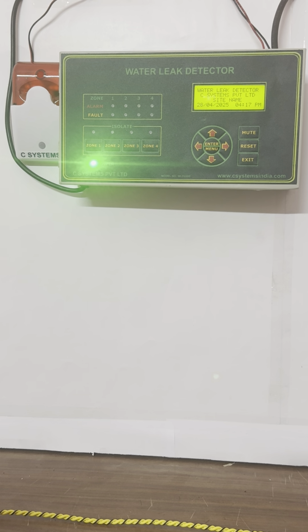I'll explain in detail the panel fascia features as well as the hardware input output features in the water leak detection system. The panel is equipped with a 4x20 LCD display and keypads with LED indication for each zone, alarm and fault condition. Apart from the alarm and fault indication, there is a provision for isolating each zone individually, which is provided in the zone 1 to zone 4 isolate buttons.